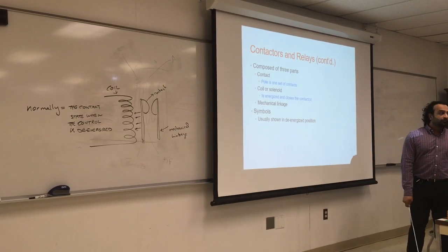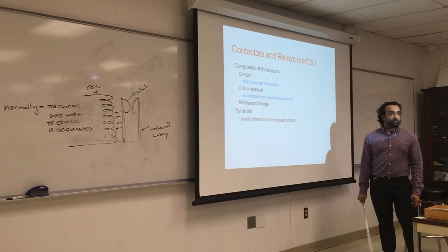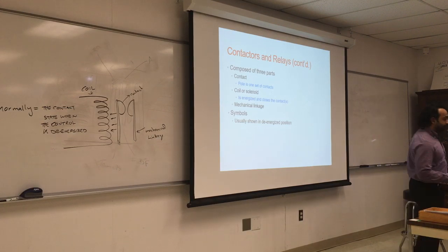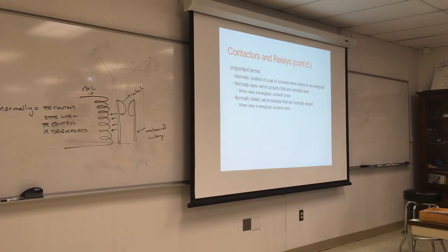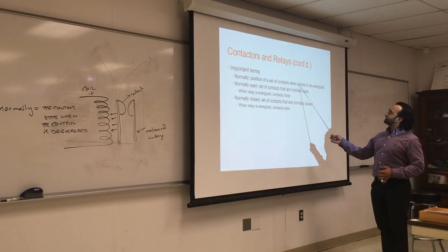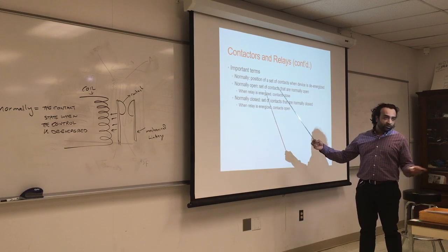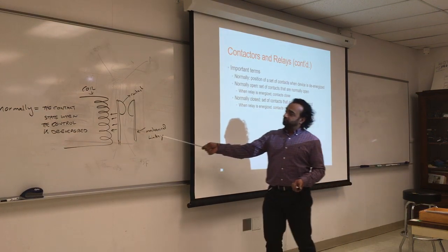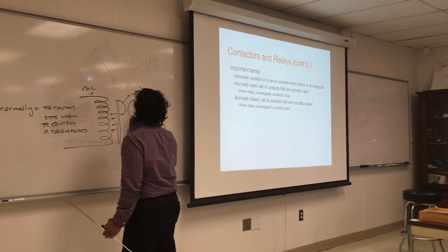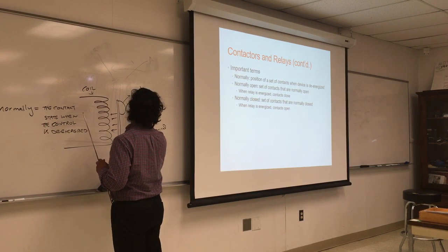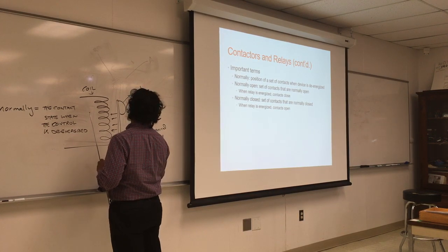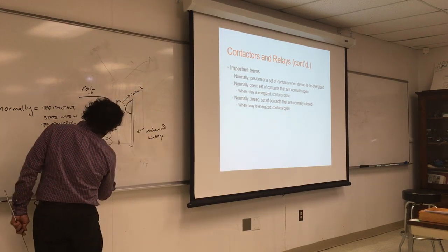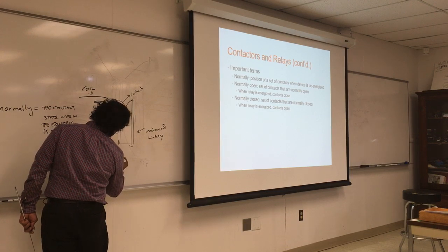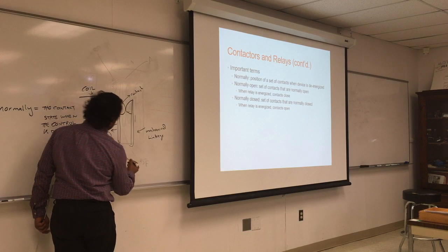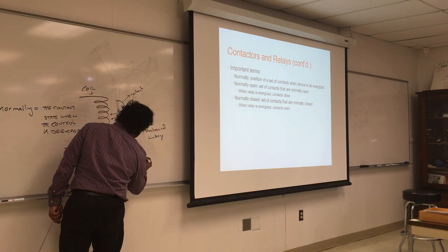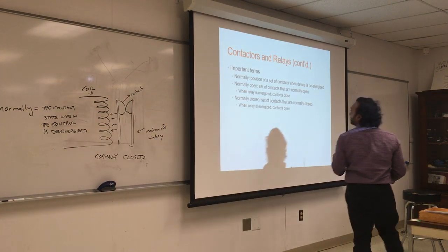Symbols. Usually, whatever is sketched on the relay is how it is when it's de-energized, which is the normal state. So normally, it's the position when the set of contacts of the device is de-energized. Normally open, when it's de-energized, open. So this is normally open. This is a really bad schematic. It should touch. Okay, so this is normally closed.